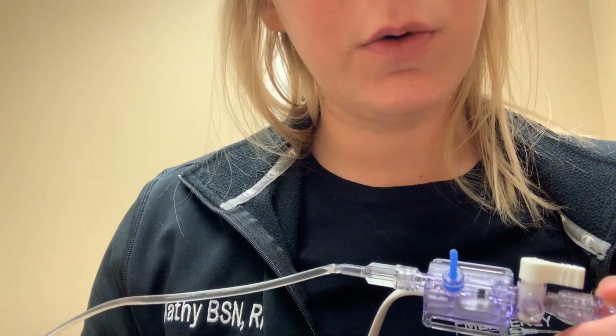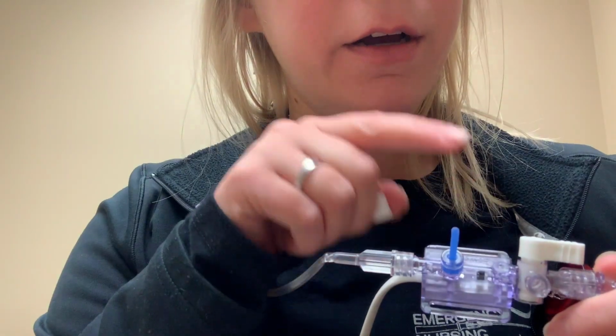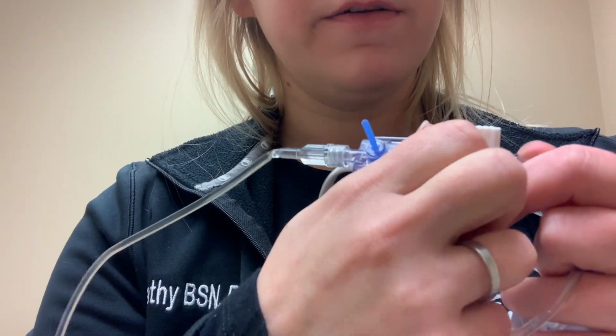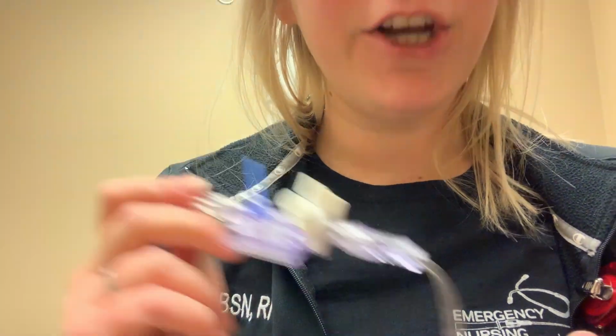Okay, so now we are gonna press the 0 button on our monitor, because zeroing means that it is getting adjusted to the atmospheric pressure so that we make sure that we have the right blood pressures essentially. So I'm gonna undo this cap. You're gonna zero it out. It's gonna beep. It's gonna have a straight line. You're gonna recap it. Oops, sorry guys. You're gonna recap it here. You're gonna go off to atmospheric pressure and you're gonna watch your monitor and you're gonna get a waveform and you're gonna get readings, okay?